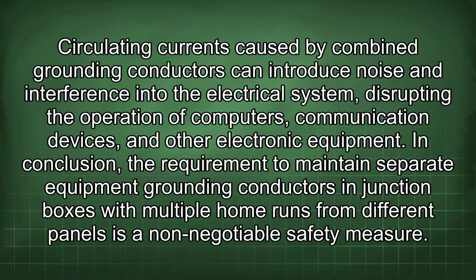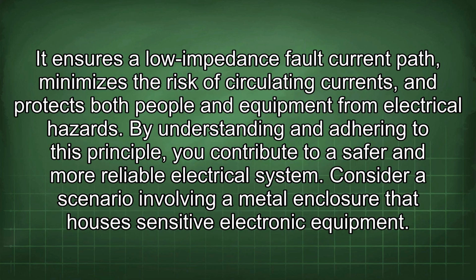In conclusion, the requirement to maintain separate equipment grounding conductors in junction boxes with multiple home runs from different panels is a non-negotiable safety measure. It ensures a low impedance fault current path, minimizes the risk of circulating currents, and protects both people and equipment from electrical hazards. By understanding and adhering to this principle, you contribute to a safer and more reliable electrical system.